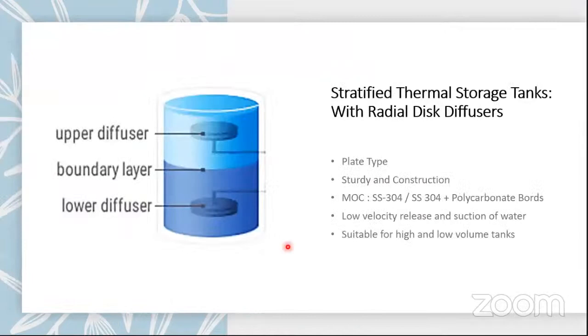And then we have stratified thermal storage tanks with radial disc diffusers. You see in this picture here, these are plate type diffusers, radial in construction. They are sturdy in construction because they are of SS, either only SS or a combination of SS and polycarbonate boards. The objective of these diffusers is to release the water inside with a very low velocity and very low release and suction of water, and it is suitable for high and low volume tanks.